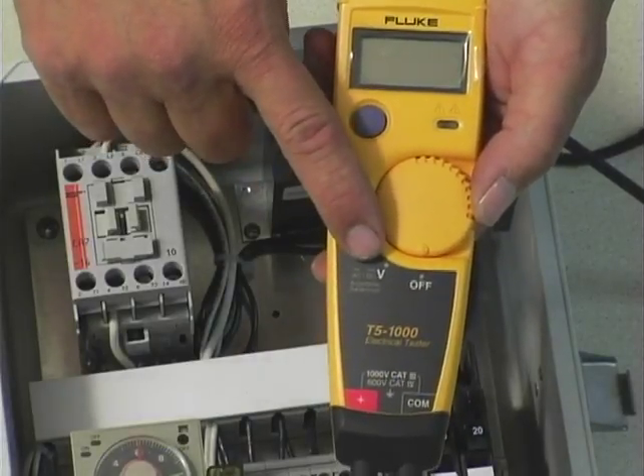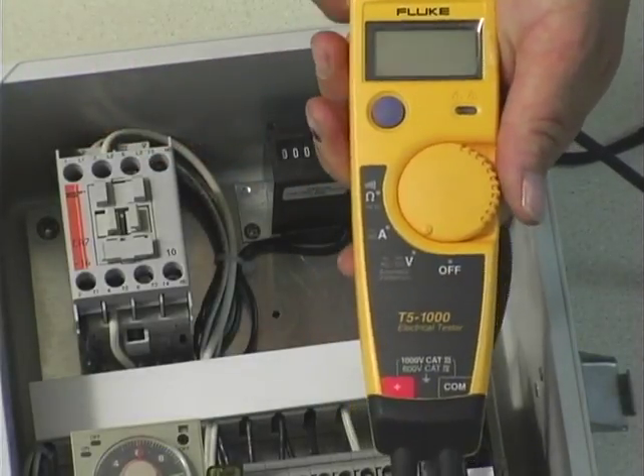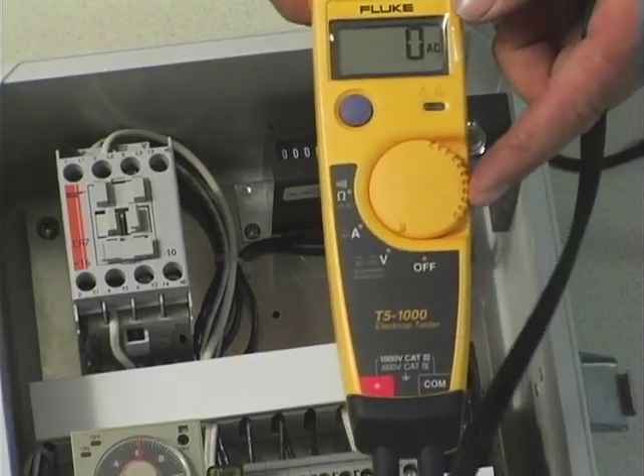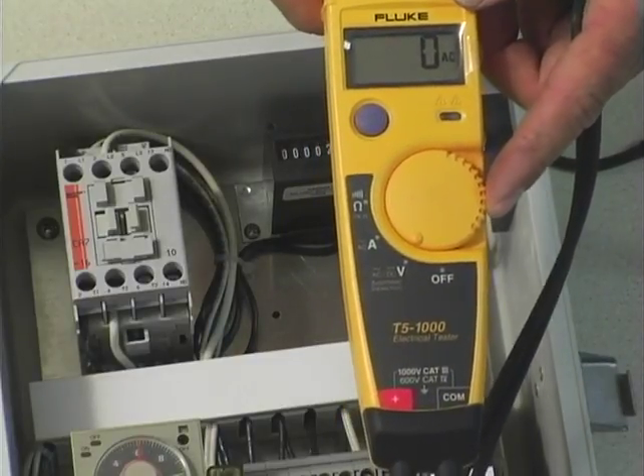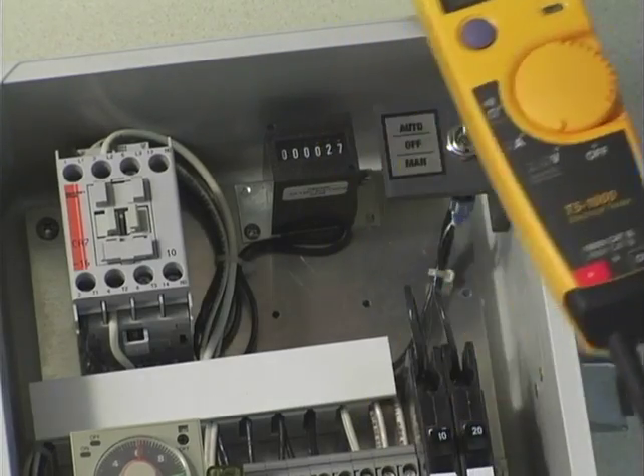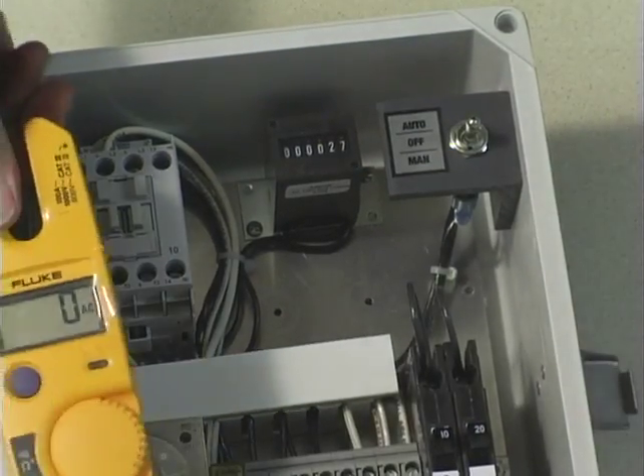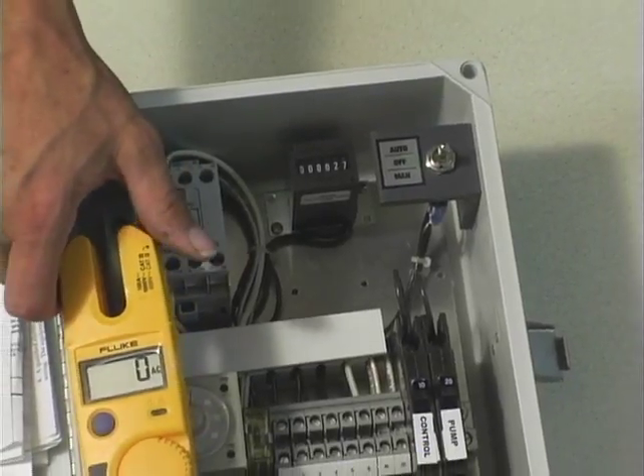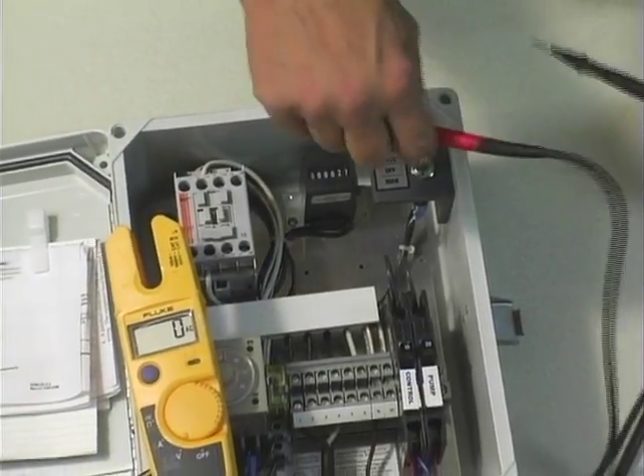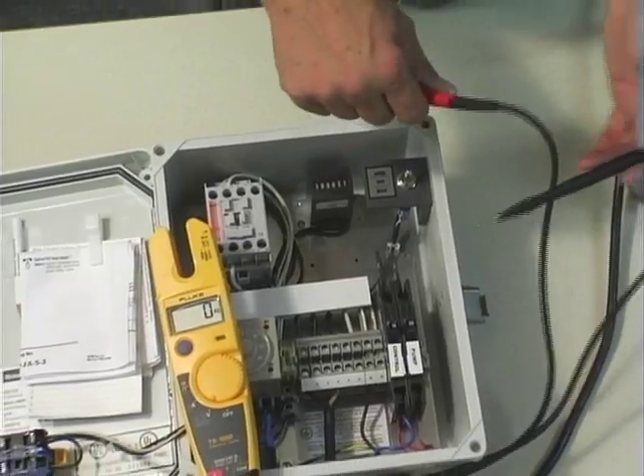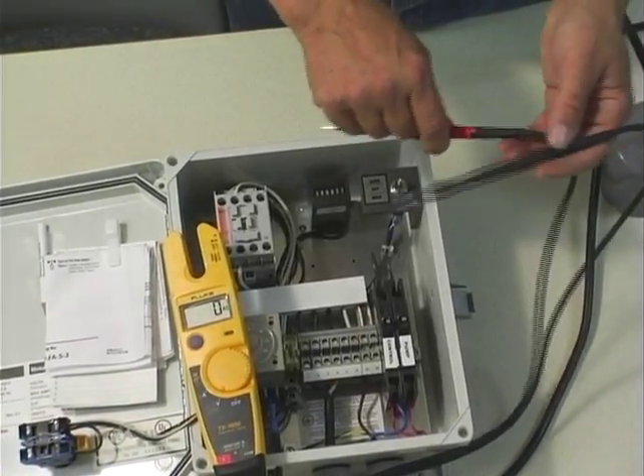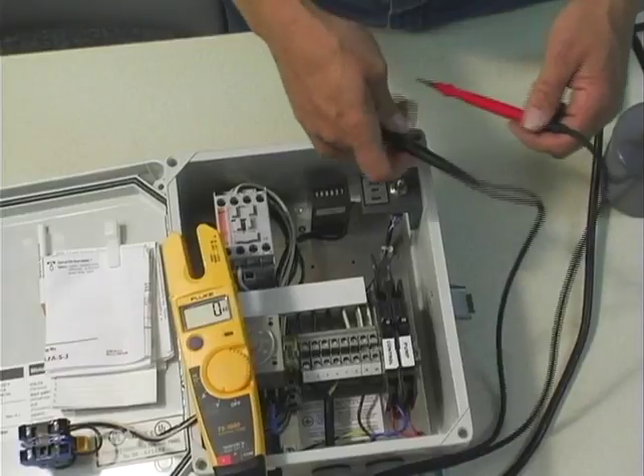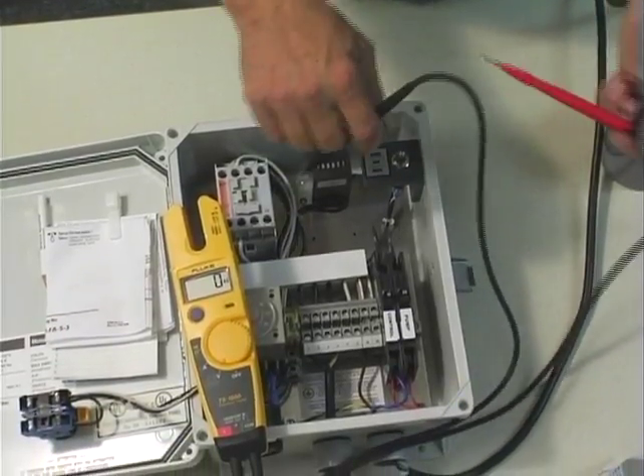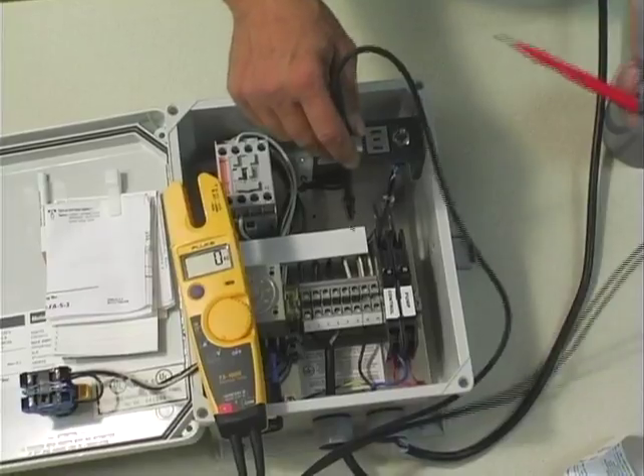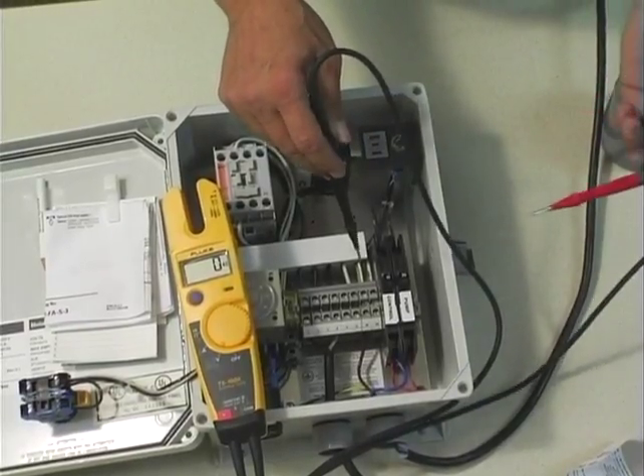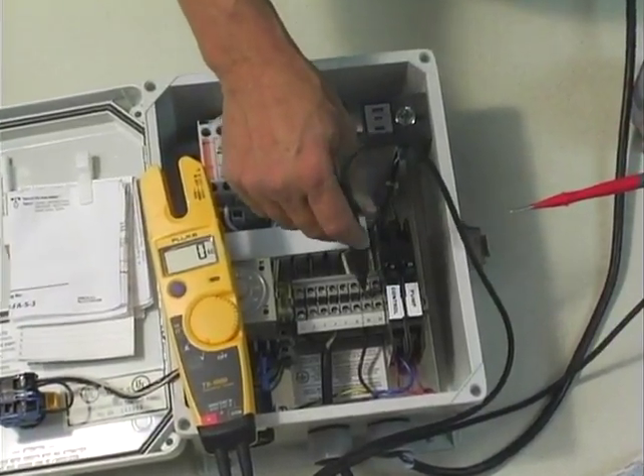First thing we want to do is take our meter and switch it to voltage. This particular meter will register either AC or DC, and we're going to check for voltage in the control panel. Now what we want to check for, and this is over and over again, you only want to check to neutral. A lot of times the control panel, if you check it to ground, it will register as 120 volts, but if you check it to neutral and there's no neutral wire present, then you'll get a 0 reading right away, and that's the fastest way to know if you don't have electricity.